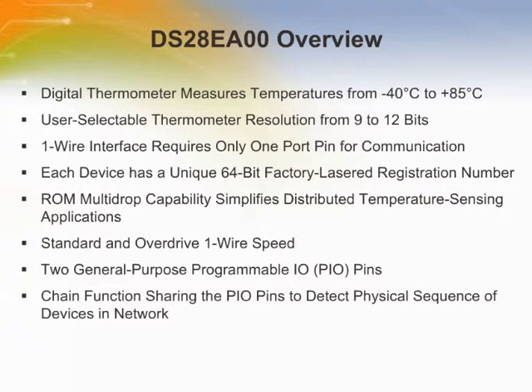The DS28EA00 measures temperatures over the minus 40 degrees C to 85 degrees C range and has user programmable analog to digital conversion resolution with 9-bit to 12-bit options. It operates over Maxim's one-wire interface with a protocol that delivers power as well as communication over a single connection. It has a unique 64-bit internal serial number that is used in a multi-drop environment to select a specific device for temperature results.